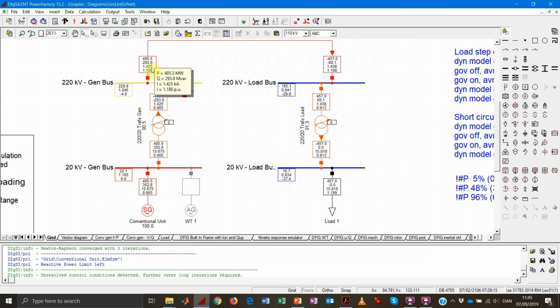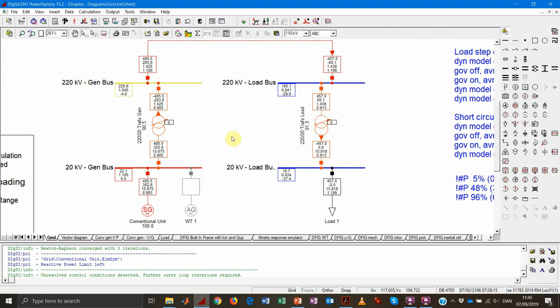You can see that the line is absorbing 293 MVAR and releasing only 60 MVAR on the other end, meaning it is consuming 233.7 MVAR by itself — plus some active power losses. But of course, the voltage values are unacceptable: one end exceeds 1.1 per unit while the other is way below 90%, which would not be acceptable. This is definitely not an acceptable operating point.